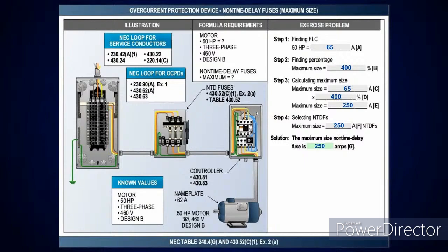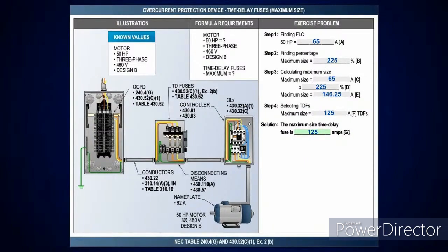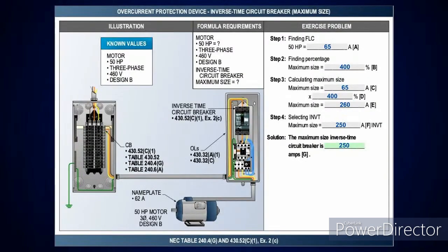Okay? Now, if I come over here and I look at my time delay fuses, and you come down and you pick up your time delay fuses, it tells you it's permitted to be increased, but in no case shall it exceed 225%. So I take 65 amps at 225%, it's 146.25 amps. The next size below that, per Table 240.6(A) where your standard overcurrent device ratings are, that'll be a 125 amp overcurrent device. And then when I get to my inverse time circuit breakers, it's exactly the same thing, just like I had for that.